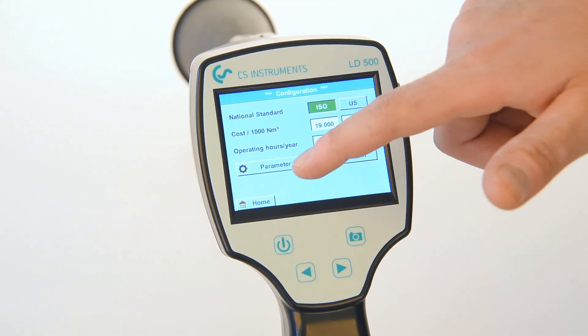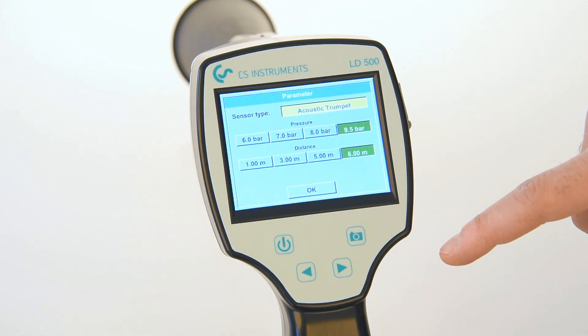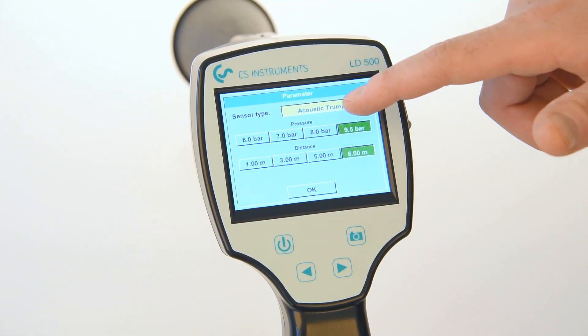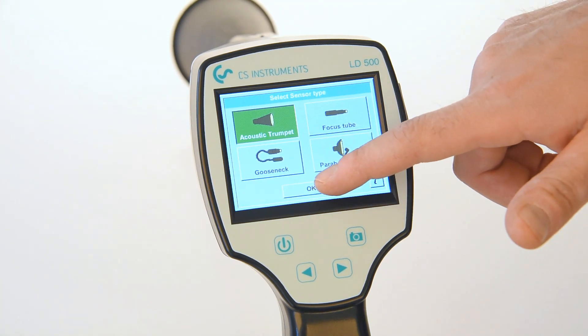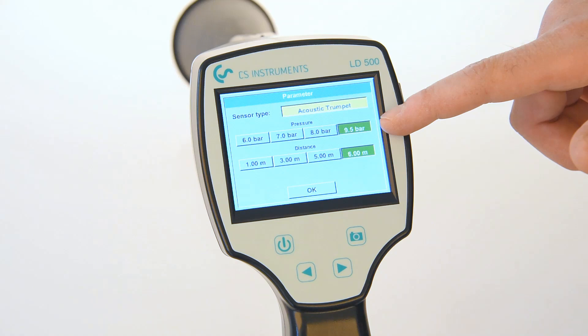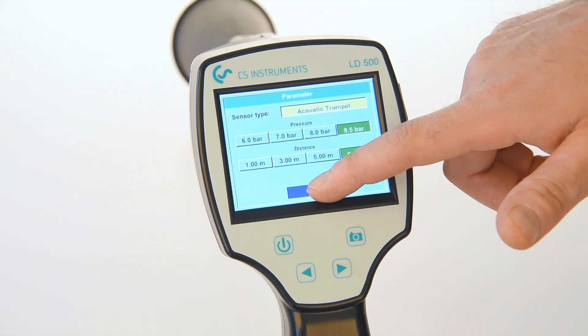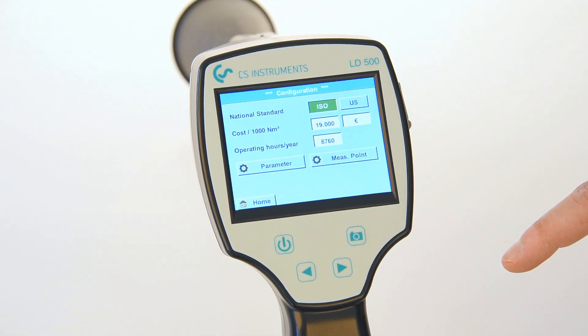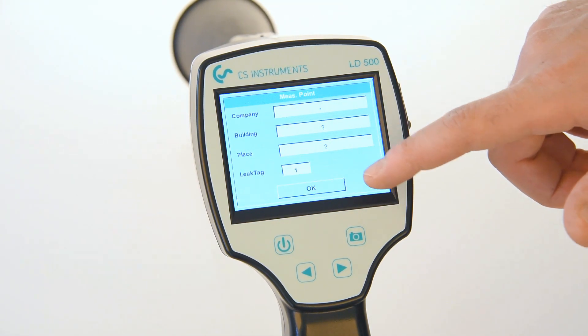The sub-menu labeled 'Parameters' is there to select the correct sensor which is currently attached to the instrument. The selection of the right sensor for each measuring task is explained in detail during our first demo video. The running pressure of the compressed air system needs to be selected as well as the approximate distance to the leak.